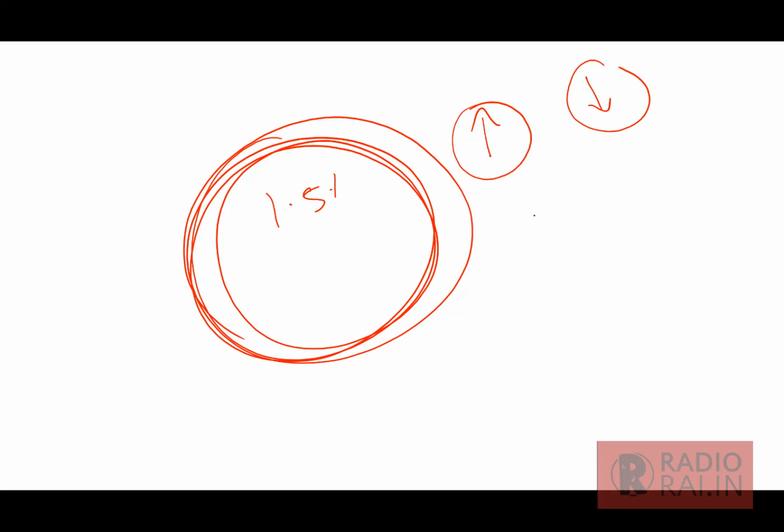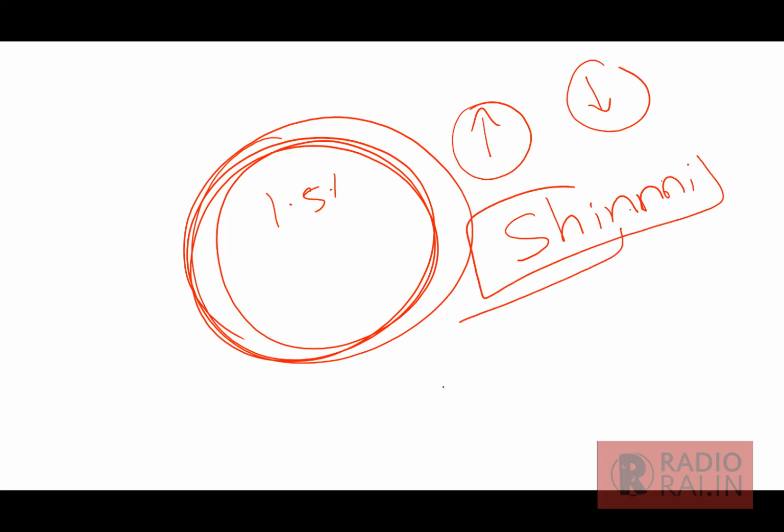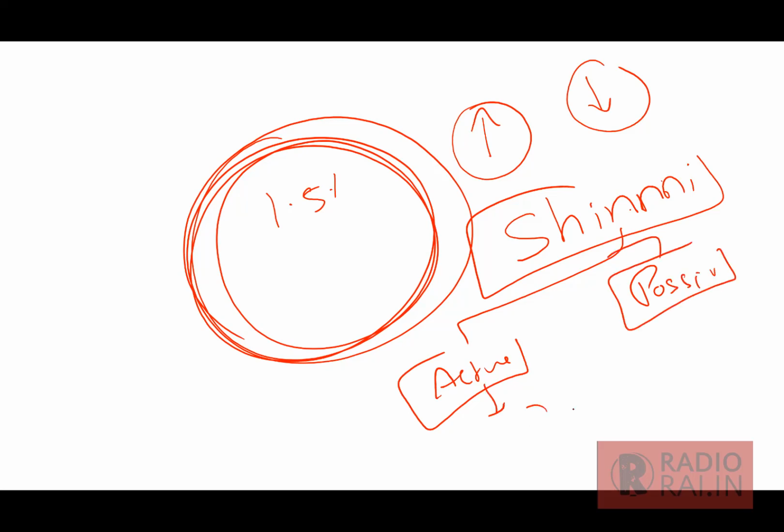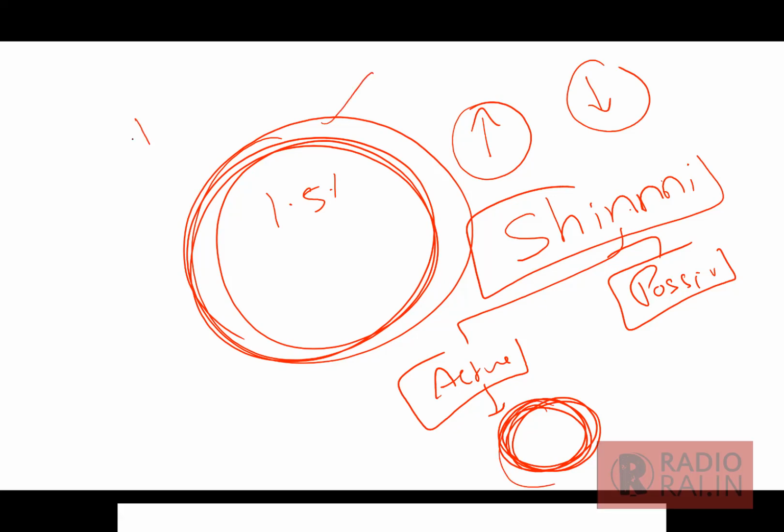By a technique called shimming. Shimming can be done in two ways: active shimming and passive shimming. Active shimming is when we keep one more coil which can adjust the magnetic field in the required places. If you put the coil in the same direction as the previous magnetic field, the fields add up.